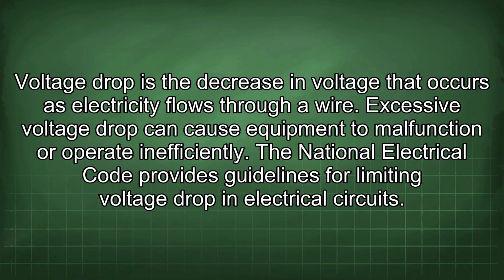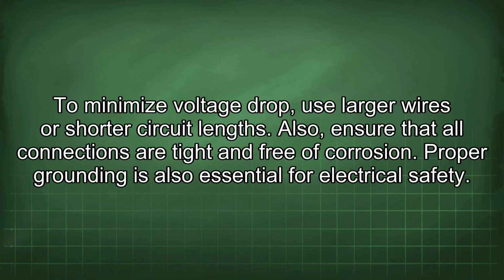Excessive voltage drop can cause equipment to malfunction or operate inefficiently. The National Electrical Code provides guidelines for limiting voltage drop in electrical circuits. To minimize voltage drop, use larger wires or shorter circuit lengths. Also, ensure that all connections are tight and free of corrosion.